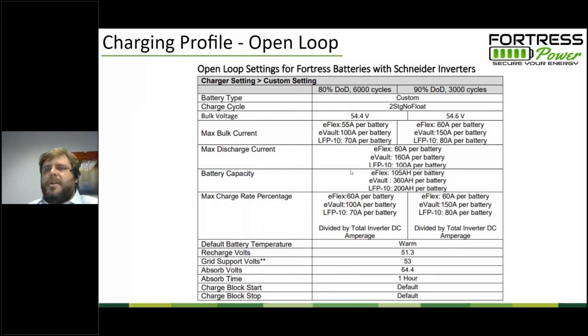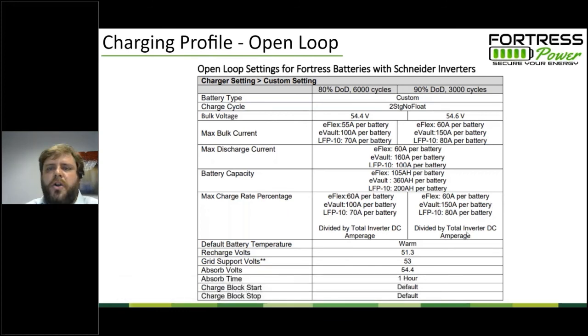Let's see some other terms on here. Our default battery temperature: we generally let the temperature controls be governed by our BMS systems for the eFlex and the eVault. And so you generally do not use a battery temperature sensor with our products. Then there are things like the grid support voltage or the recharge voltage. The grid support voltage works like this: if the battery is over this voltage, sell back to the grid. The recharge voltage works like this: if the battery is below a particular voltage, recharge from the grid.